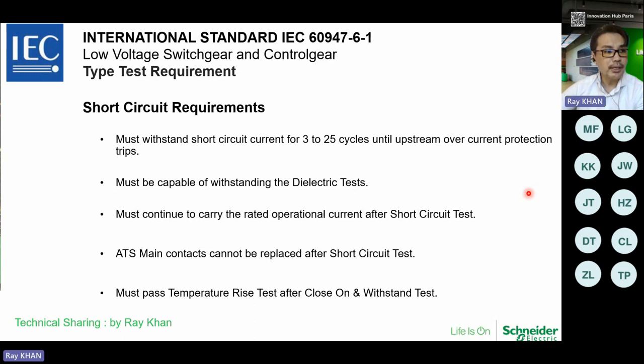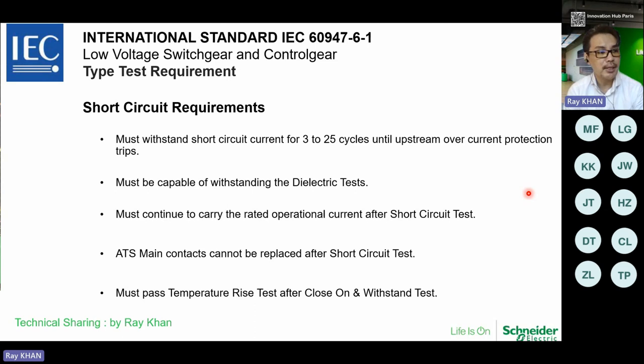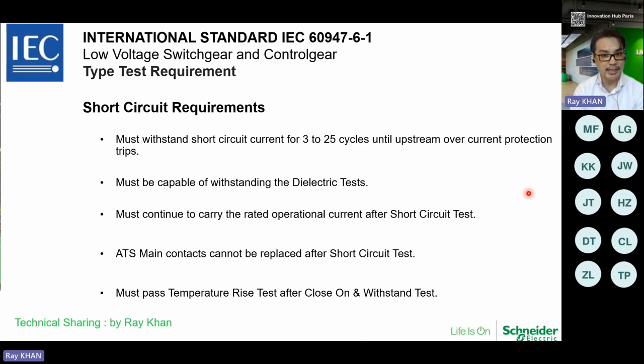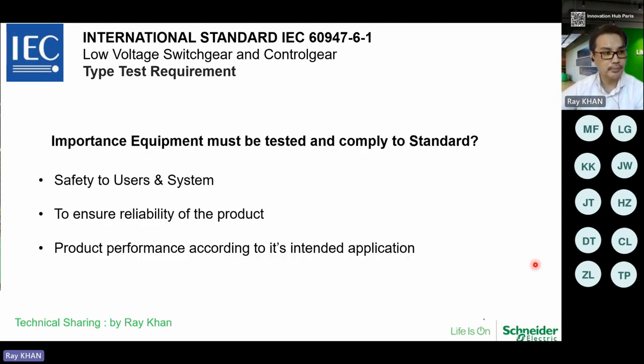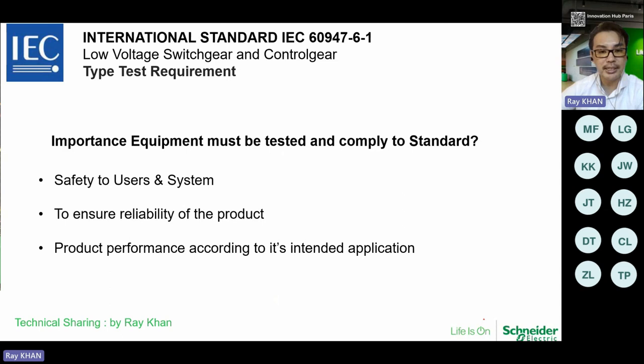In the short-circuit requirement, key points are: it must withstand short-circuit currents for 3 to 25 cycles until the upstream overcurrent protection trips; it must be capable of withstanding dielectric tests; it must continue to carry rated operational current after short-circuit tests; the ATS main contacts cannot be replaced after short-circuit tests; and it must pass temperature rise tests after close on and withstand tests.